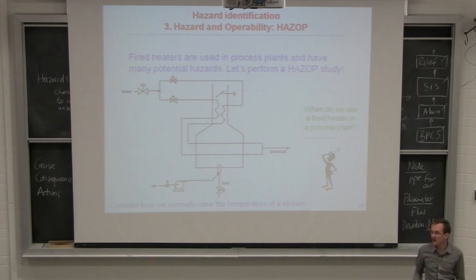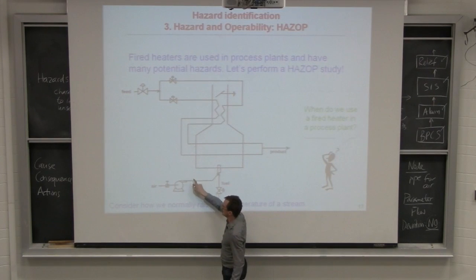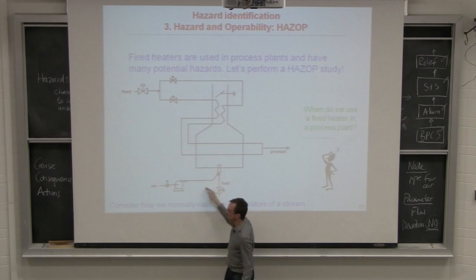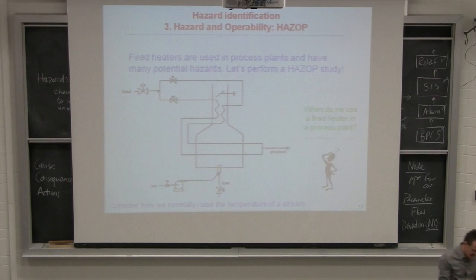Okay, there's also a safety interlock that you could put on the system. So, a safety interlock that will measure the air flow, if it's not at the required level, shut the fuel, open the air. Okay, so there's a number of actions, then, that you would take on that. Some are more costly than others. Okay, so that's the idea with hazard and operability studies.